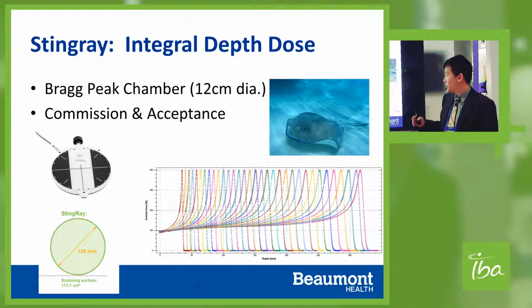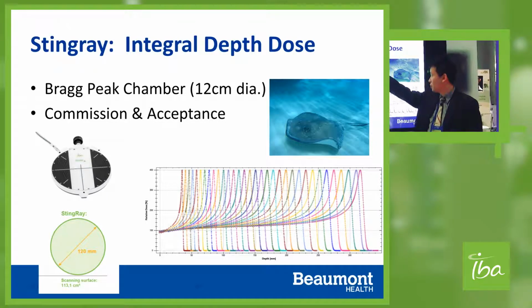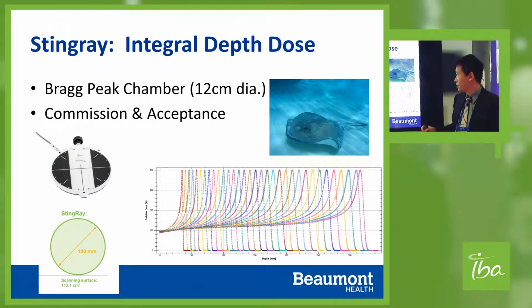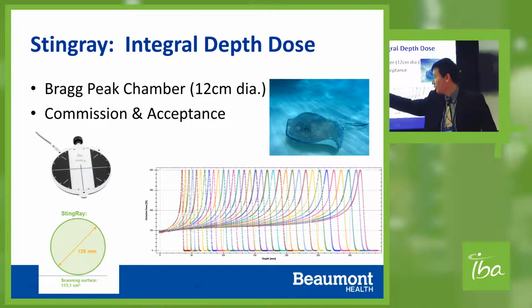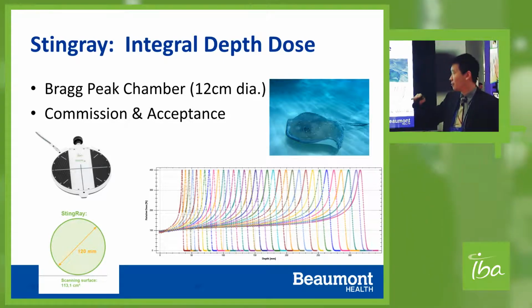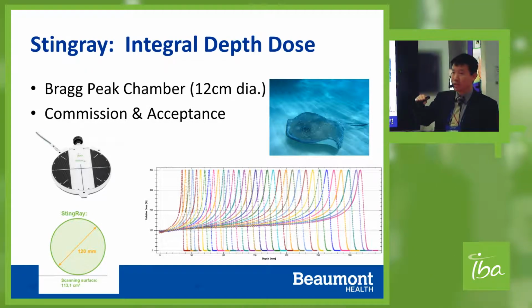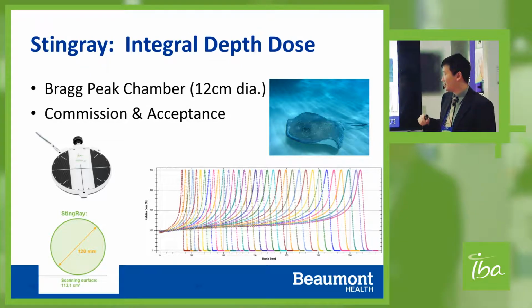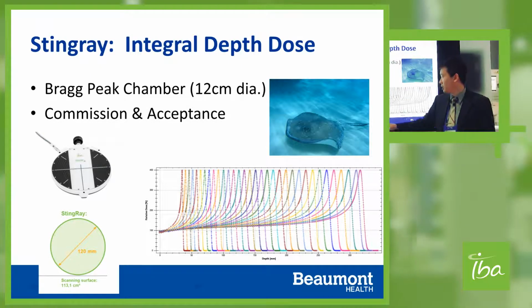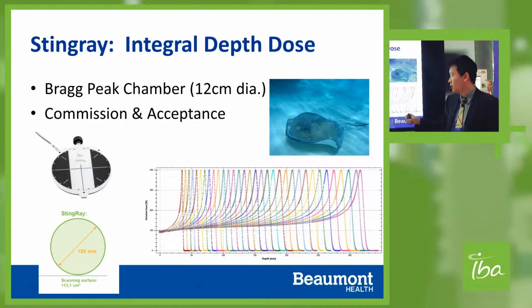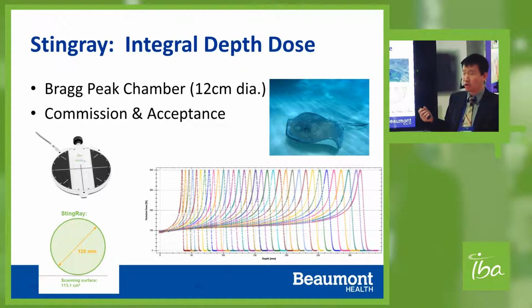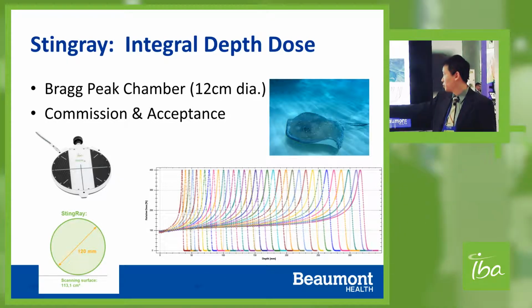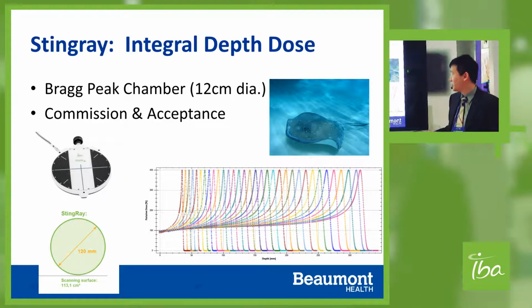And also, Stingray is actually a new device which we use in the Proteus One because we want to collect enough charge for each spot. So Stingray has a 12 cm diameter, which is very user-friendly by design. You have the 3 pins in here to help align horizontally on the water surface. So this is going to be really critical for your setup. And also the 12 cm diameter helps you to collect all the charge whether your spot size is bigger or smaller. So this is the integral data we collected for our Proteus One for different energy layers.